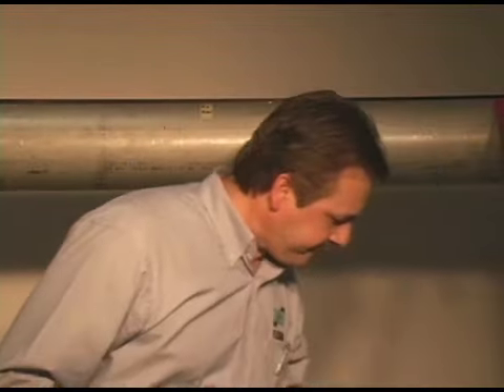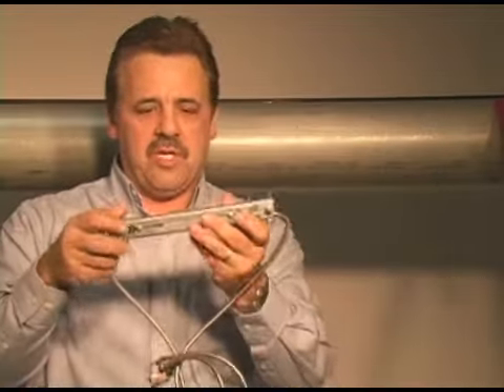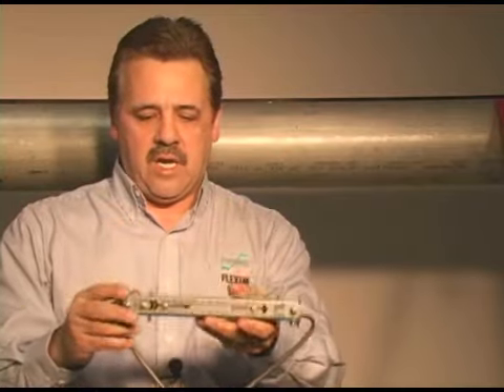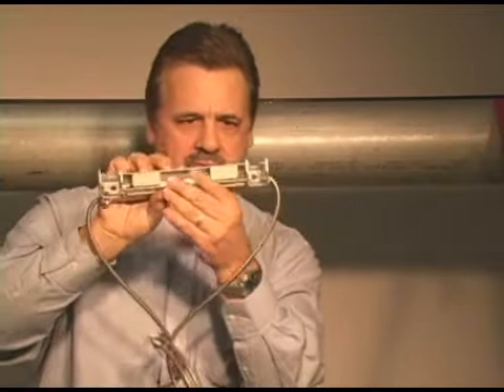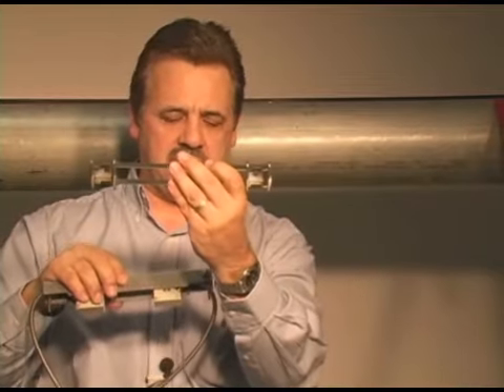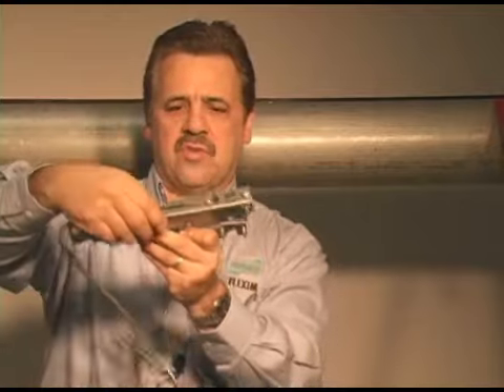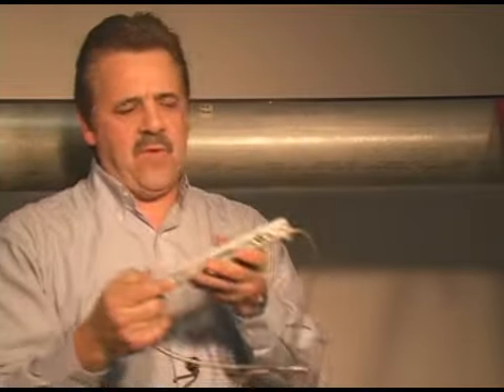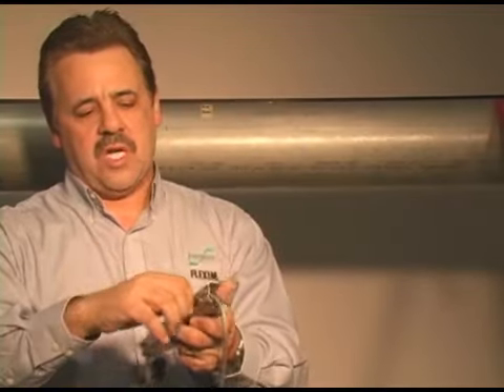Okay, I'm going to opt for the single mounting solution here to demonstrate to you. Here's the track assembly completed with the transducers mounted in. It comes apart into two sections. This is the base section that installs to the pipe, and the transducers will then come over on the top. If you have to remove a transducer because you're going to use a second track, if you remove this screw here, the transducer will come straight out with the mounting hardware.